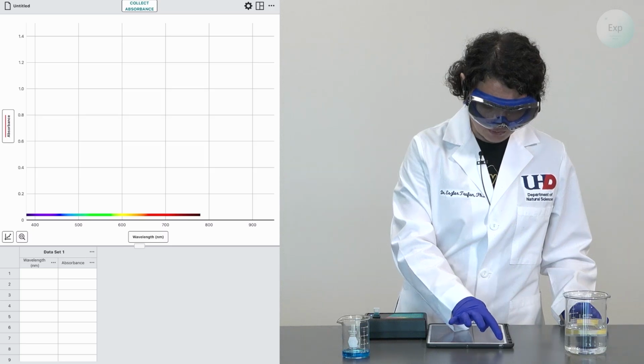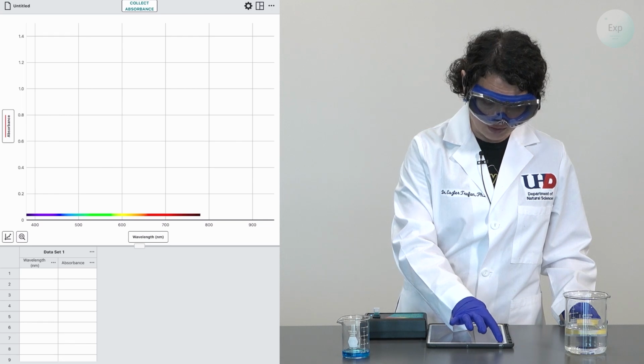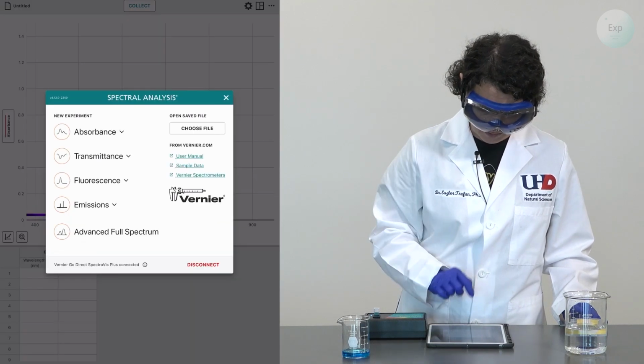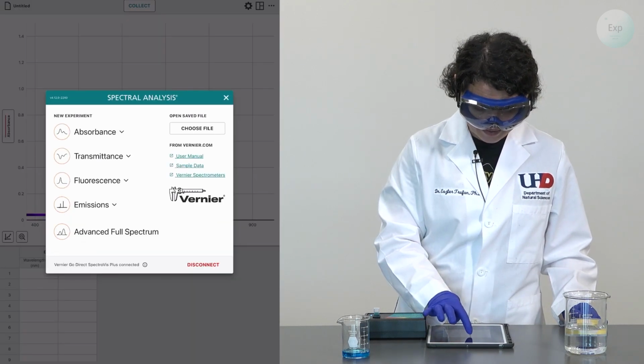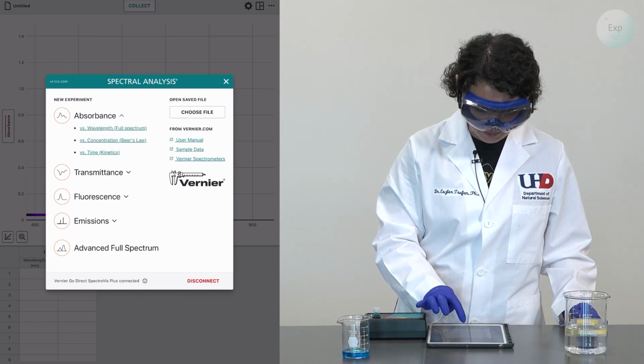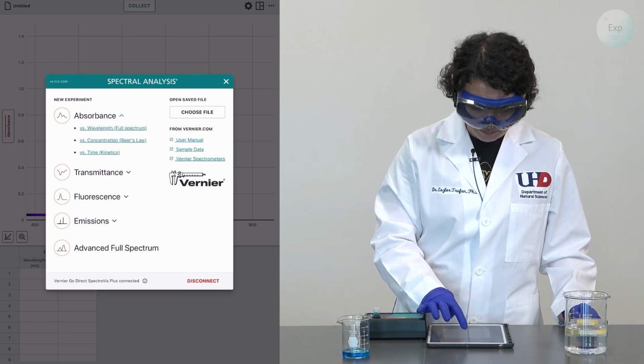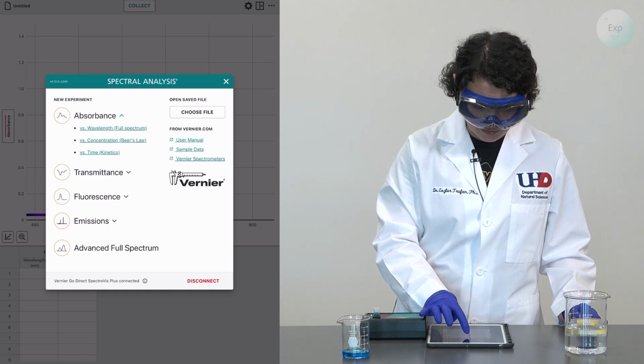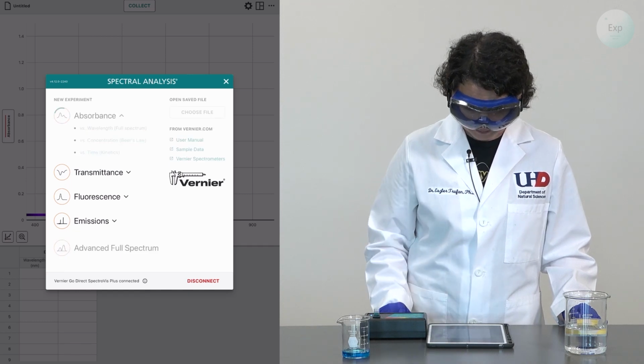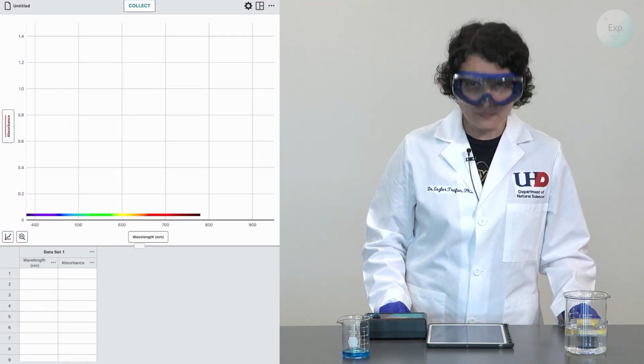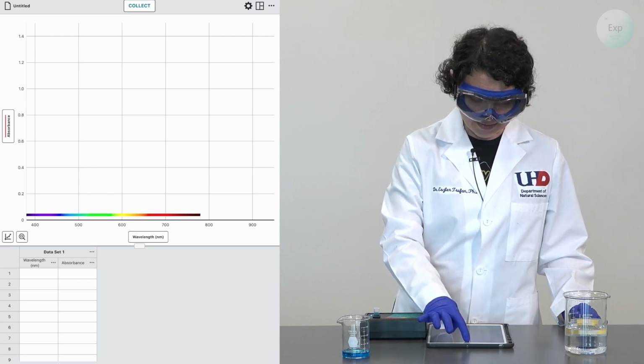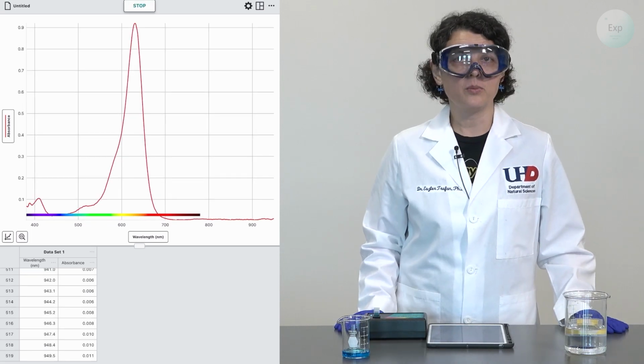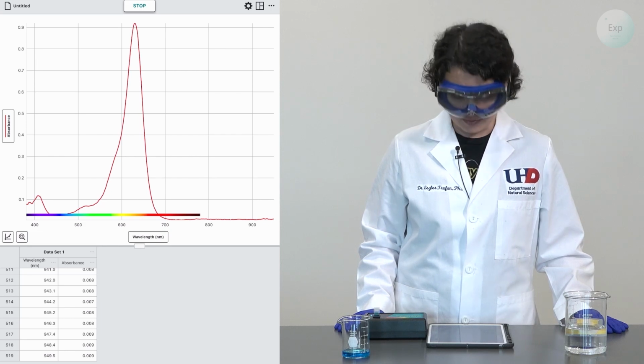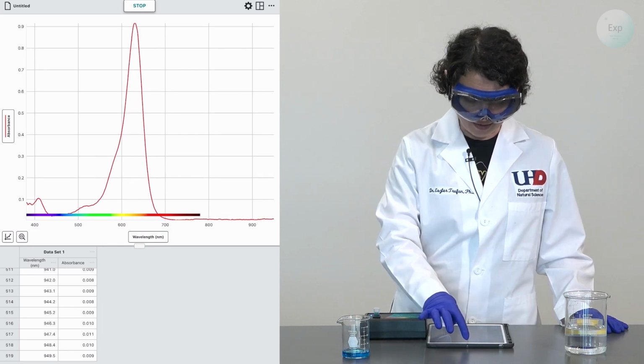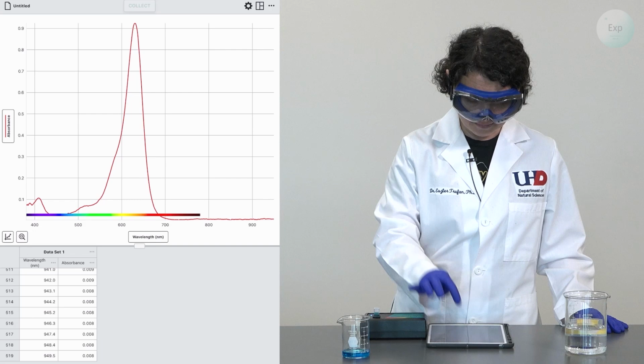We're going to go to the top left of our page on the display, select New Experiment, then we'll press the down arrow under Absorbance. And when it pulls up the three options, we will select the top one, versus wavelength full spectrum. When the page opens, we press collect, and a spectrum will be automatically generated for us. Once we press stop, that data is finalized.